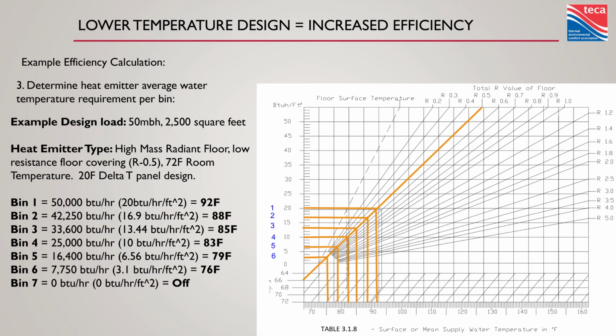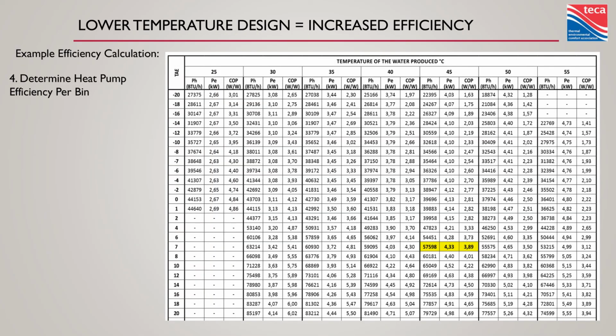Meanwhile, bin 4, not the burger joint, only needs 83 degree water. So that's where our outdoor reset control strategy really shines. We're getting more capacity from the heat pump, more efficiency from the heat pump, just by dropping that leaving water temperature. So then we can go to this heat pump chart, take a look at each one of those bins. How much capacity do I have at that outdoor temperature and that corresponding leaving water temperature? And we can start plunking some numbers in.